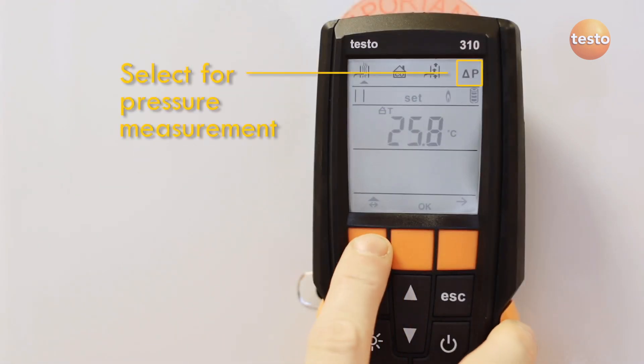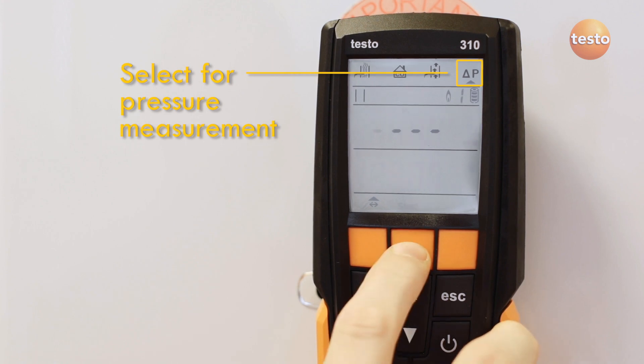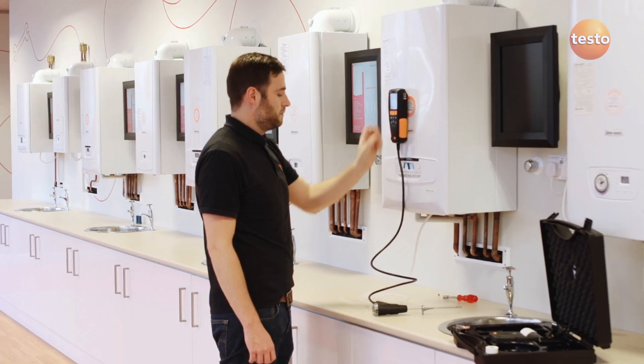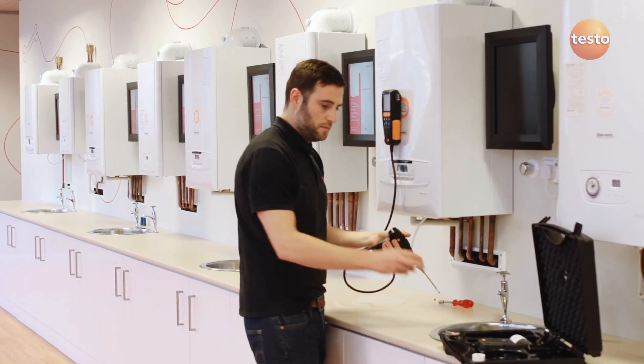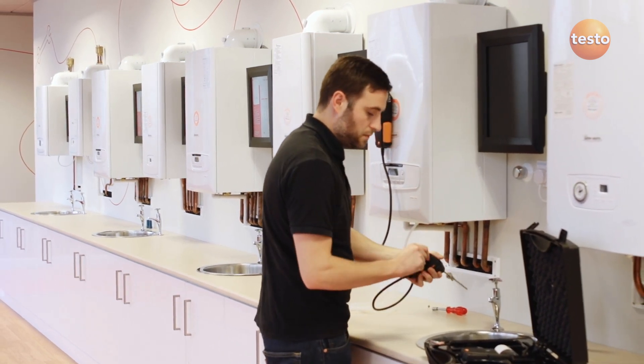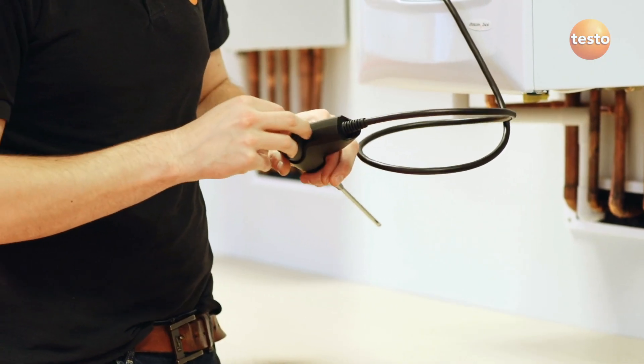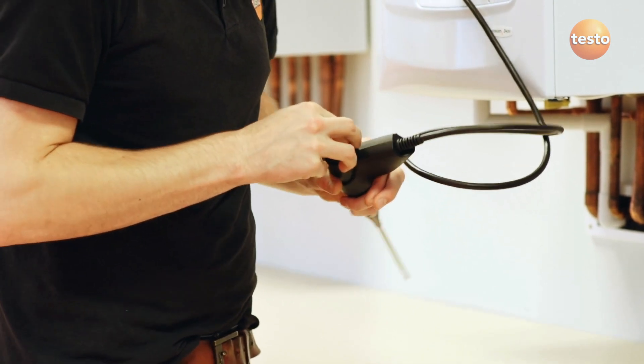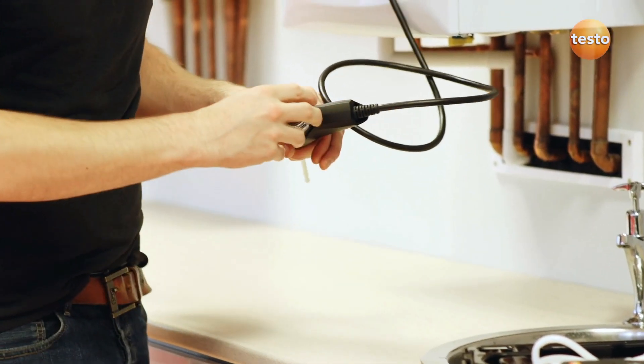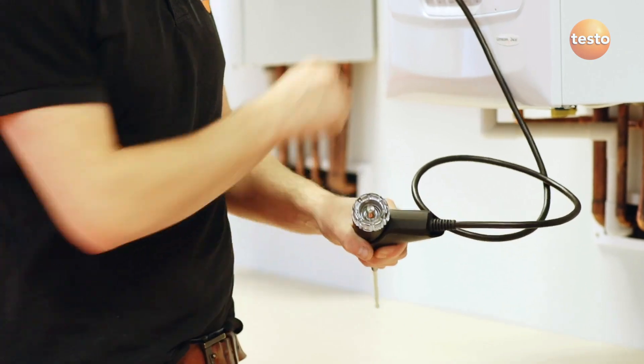To measure gas pressure, select the pressure test mode, which causes the 310 to remind you to fit the pressure plug in the probe. This seals off the gas path to allow pressure to be measured. Remove the filter and put the orange plug into the hole in the center of the probe handle.